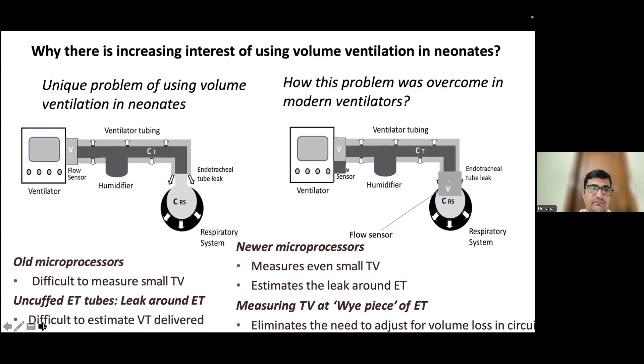Since these flow sensors are measuring the tidal volume at the level of the patient, they eliminate the need to adjust for volume loss in the circuit. Whenever the previous ventilators were in use, in which the flow sensors were within the machine, clinicians used to give a tidal volume of 10 to 12 ml per kg. They gave a very high tidal volume so that the volume delivered to the baby came to somewhere like 4 to 6 ml per kg, overcoming the compression of gases in the circuit and humidifier as well as the circuit compliance. Whereas in present volume control ventilation, this problem has been eliminated because of placement of the flow sensor close to the patient end.